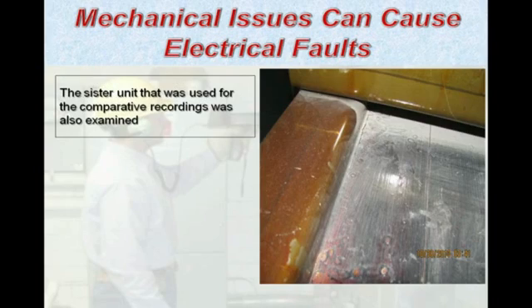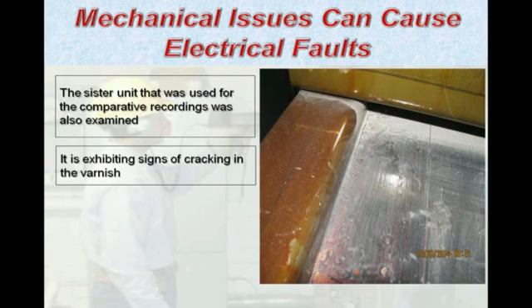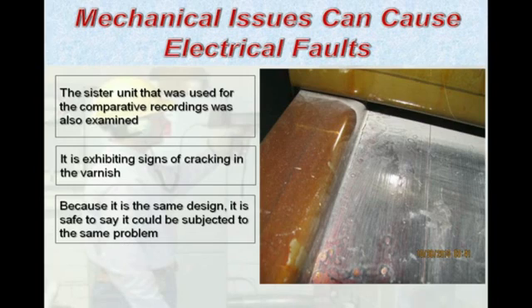The sister unit that we listened to earlier for the comparative recordings was also examined at the time of the shutdown, and what we saw was that it was exhibiting signs of cracking in the varnish already. And on this image, you can see the cracks toward the top center of the image, but there's no separation here at this point. That is not to say that this will not occur in the future, as these units were of the same generation, and remember, they are running at the same loads in the same environment. So it's being exposed to the same things, and already there's early evidence we're going to see the same delamination of the core within this unit, and it could possibly be the same defect in the manufacturing with the miter joint that we've seen earlier. So it's safe to say it's going to be subject to the same problem as time goes by.